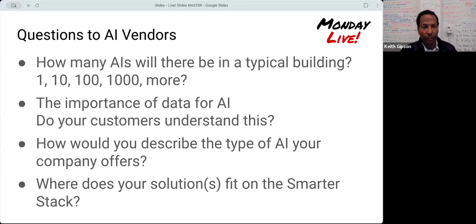Absolutely. If you didn't filter out bad data, like you do in a meter reading system where you have a resolution and a tolerance, our AI just ignores bad data like that. And it only needs about 80 to 85% data quality to be quite effective, which falls right in the realm of most building control systems. I had 16,000 buildings connected together at my last company, and the best we could do is 85% data quality, and that's pretty darn good. That's good enough for an AI system or a remote control system, it doesn't have to be perfect.